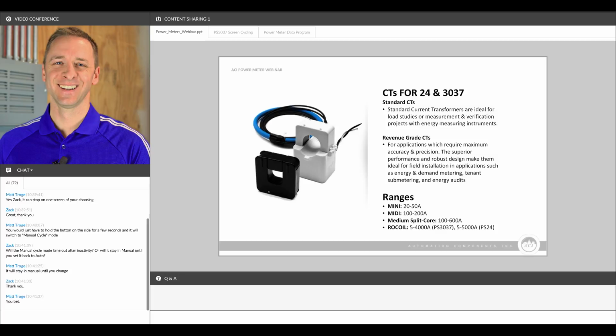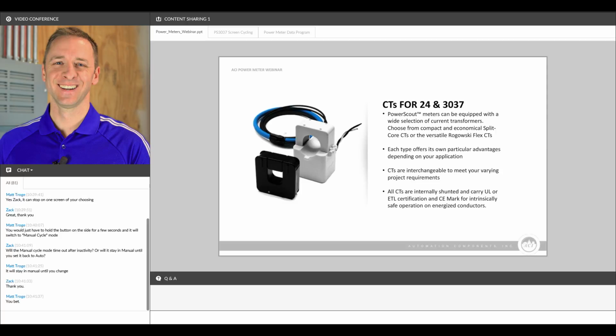The Rogowski coil CTs seem to be the type of CTs that people gravitate to, but they're not always ideal for every application. And we here at ACI are happy to discuss applications with you and help you get the best CT for your application that's going to generate the highest level of accuracy at the lowest cost. The output of the Rogowski coil CTs is scaled to between 5 and 4,000 amps when used with the PS3037, and up to 5,000 amps when used with the PS24. For the majority of applications, we're not dealing with that high of loads. We're dealing with loads in the hundreds of amps and not the thousands of amps. So in those cases, oftentimes the smaller CTs can get you a higher level of resolution and accuracy, and they're available at a lower cost as well.